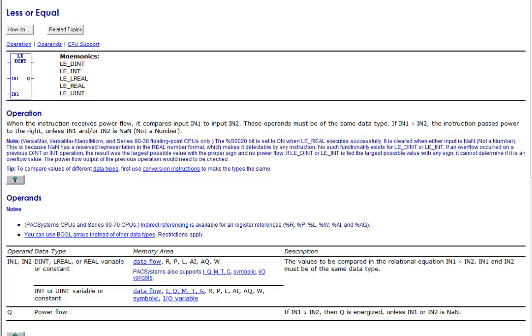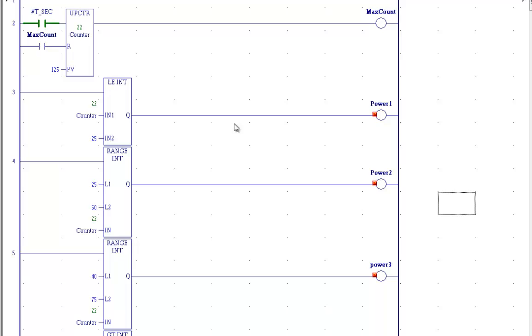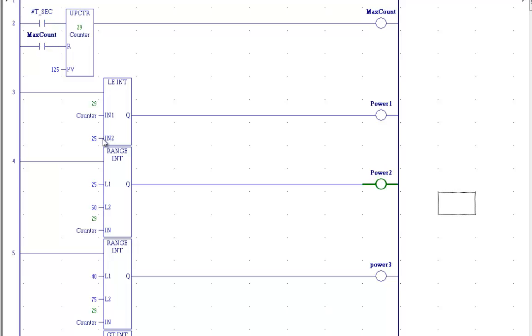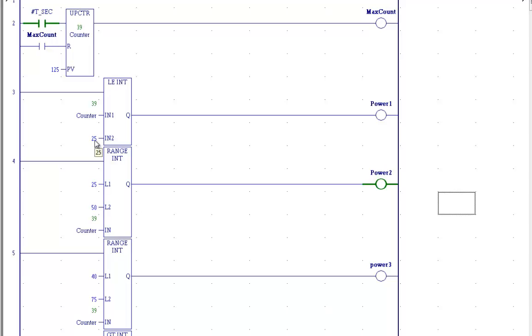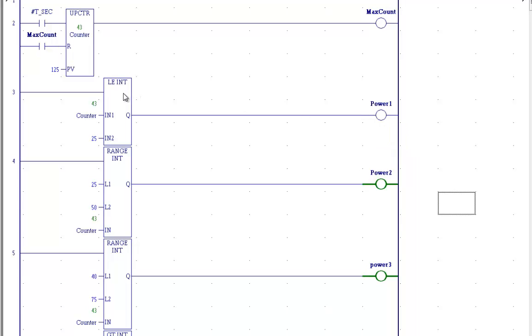It shows you here what type of data types we can use. Come back over here to the main, you see less than or equal to. So if counter is less than or equal to 25, we will have power here. You can see right now, counter is 36 and climbing, which is greater than 25, so we do not have power flow over here.